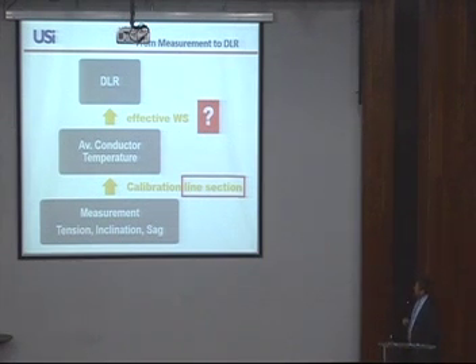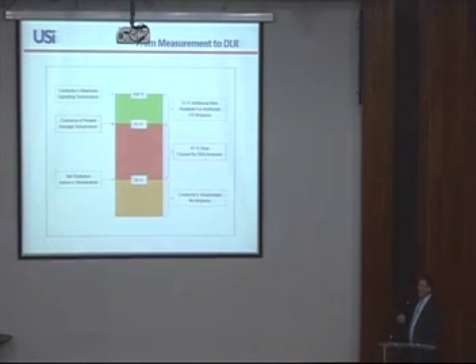What we are doing, just as an idea, we have certain measurements. Just an example here. Let's say the conductor temperature without current, you know we have a sensor there, is 30 degrees. From the tension and the calculation of a conductor temperature, we know the conductor at the moment is 75 degrees. So in Brazil, that would be already the maximum. In the US, in this case, they can go up to 100 degrees, so there is still some buffer. The 75 degrees has been caused by the current on the line and by the ambient conditions. If you take your design parameters, that means 0.6 meter per second, 35 degrees, and you take the current which you know, you will end up maybe at 90 degrees.